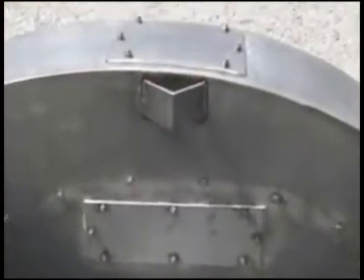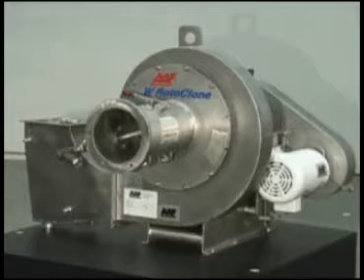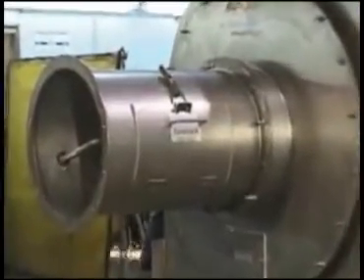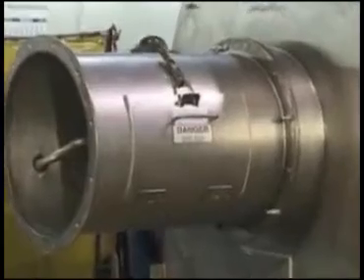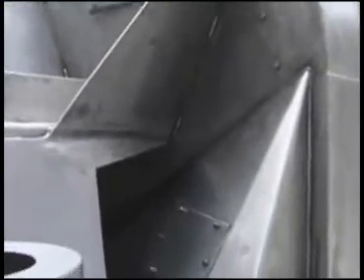The installing contractor need only bolt the Rotoclone down, connect the ductwork, make electrical connections to the Rotoclone motor, solenoid valve, and pressure or flow switch, connect to the water supply piping, and install the drains. Each W Rotoclone is equipped with a quick-opening access door to service the spray nozzles, as well as numerous bolted inspection panels strategically located on the Rotoclone for inspection and cleaning purposes.